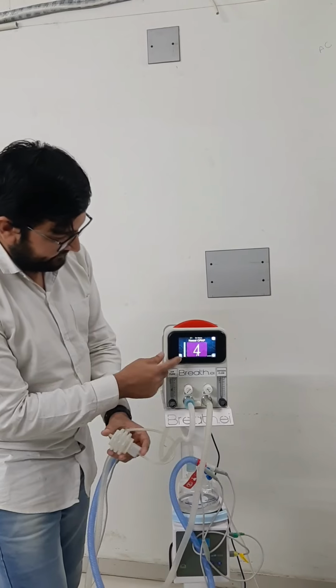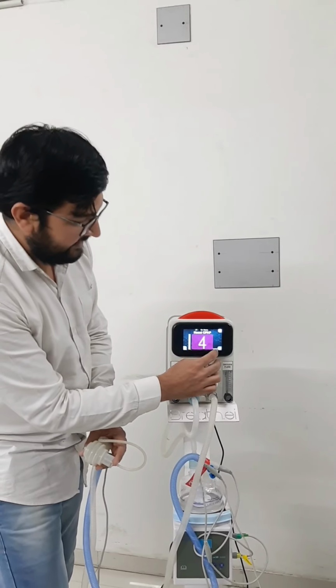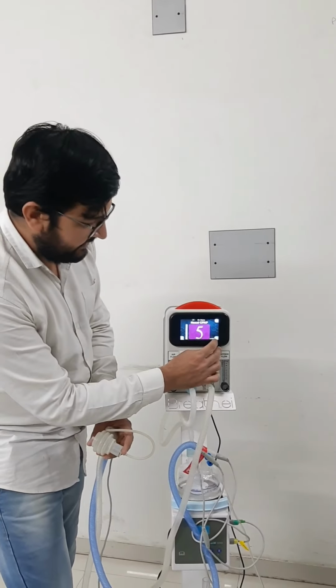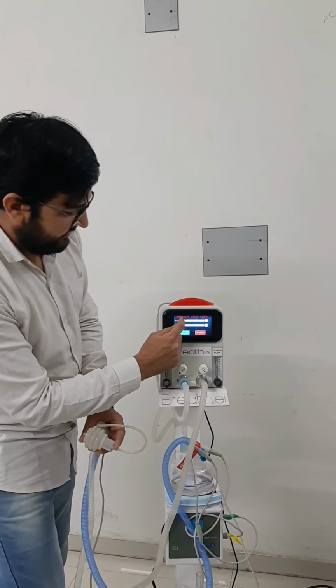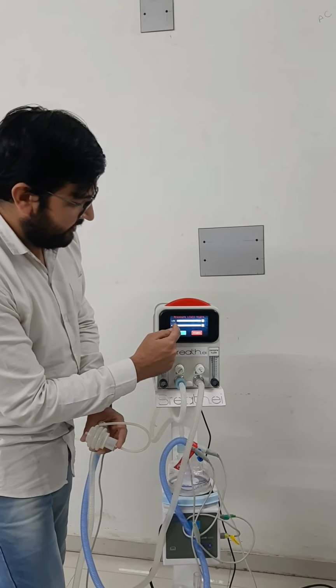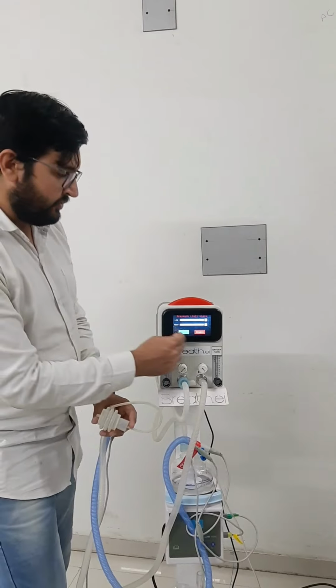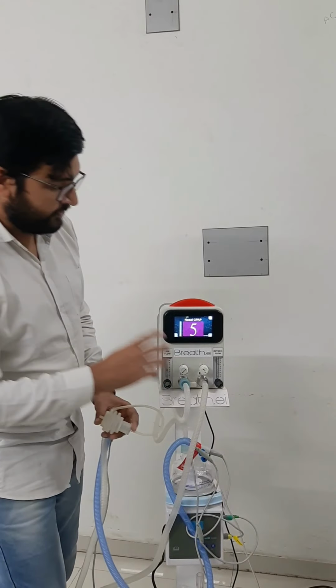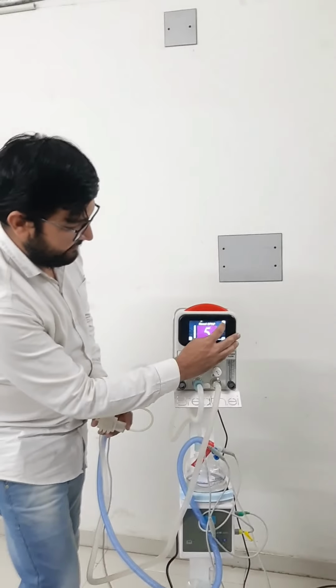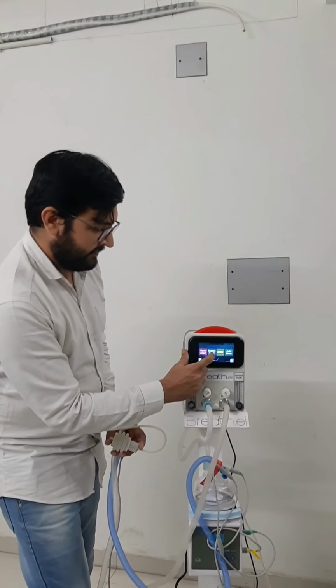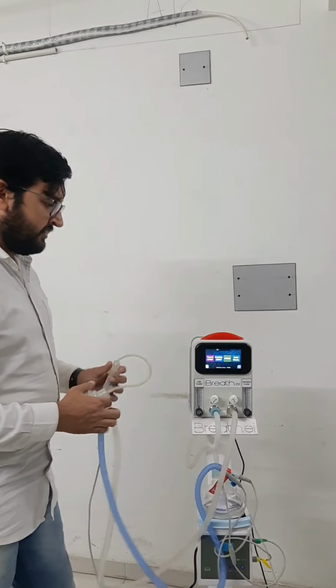bar. You can also set the alarm limit. To set the alarm limit, simply click on this alarm button and set the low pressure and high pressure limit as required. To stop the therapy, you have to click this back button and stop. So you have to stop this nasal CPAP mode.